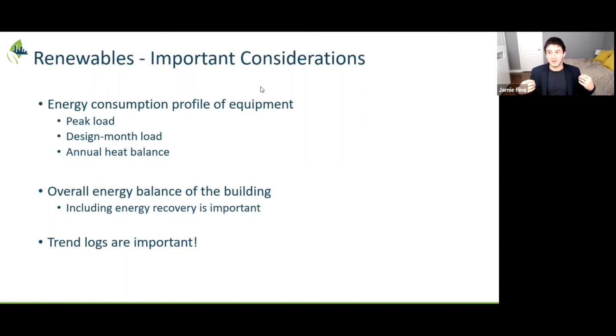So it goes back to my point that it's important to understand, and as I said before, including the effects of energy recovery because of that energy balance is very important. As was said earlier too, these trend logs are what allow you to understand how your system is performing and how you can design a system to take best advantage of your specific building, your specific climate, and your specific schedules. It's important to understand these things. Starting these trend logs and saving them at 5-minute or hourly intervals, looking at the main heat and cooling energy consumers in your building, is really important to start looking into.